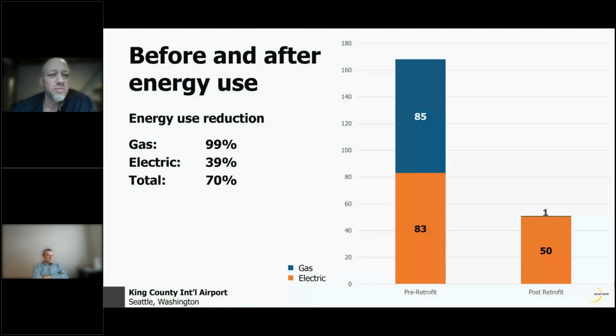It has a multi-zone system, which we don't use anymore - basically a giant air handler that makes hot and cold air, with a bunch of dampers that open and close to serve each room, mixing everything at the air handler. The EUI of this space was about 168 before we looked at it. Through mostly just a VHE DOAS and heat pump installation, we managed to get it down to 51. It's using just a tiny sliver of gas for some process load, but there's no gas for HVAC - it's all VHE DOAS and heat pumps.